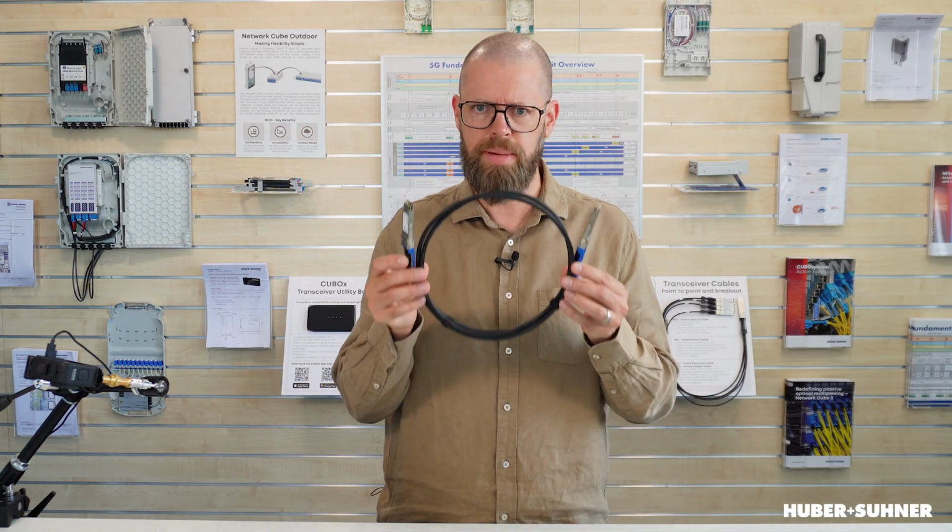And the result is that the DAC, in comparison to active optical cables, so AOCs, or traditional pluggable transceivers, is extremely price competitive. And in addition to that, the power consumption of the DAC is extremely low as well, because we're basically talking about less than 0.1 watts per side. And that's exactly what makes DACs so attractive for shorter inter- and intra-rack connections within the data center. So we've got a low cost, low power consumption solution. So what could go wrong?